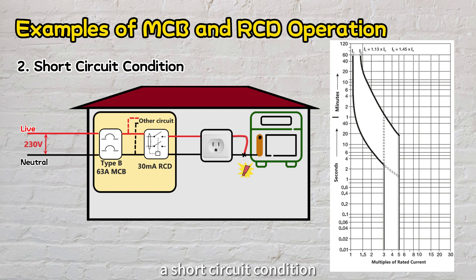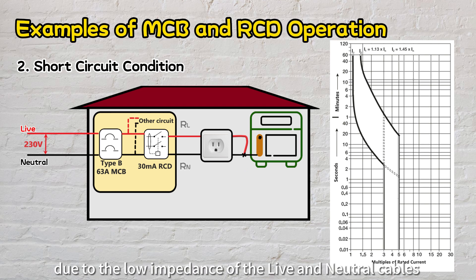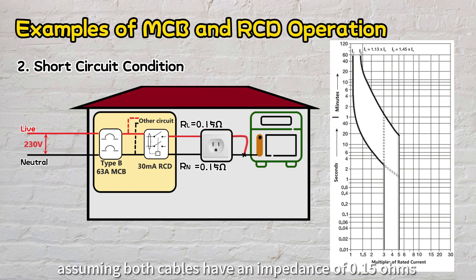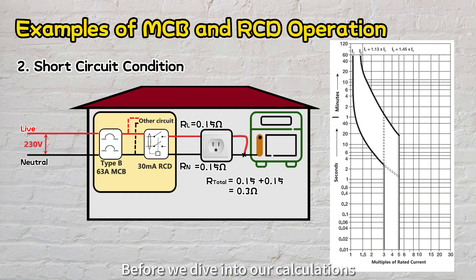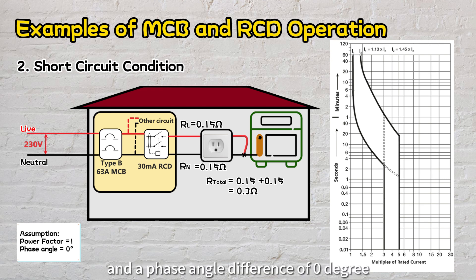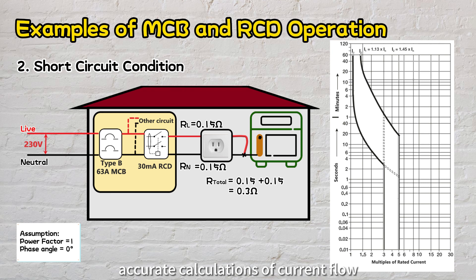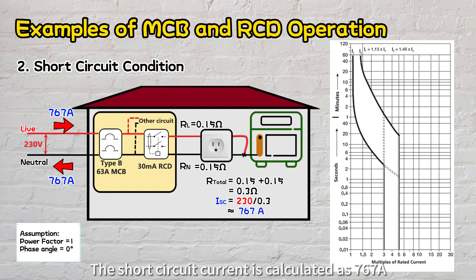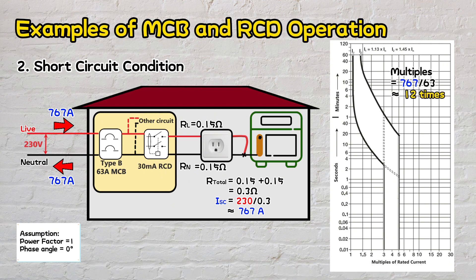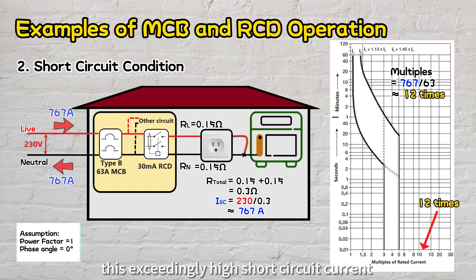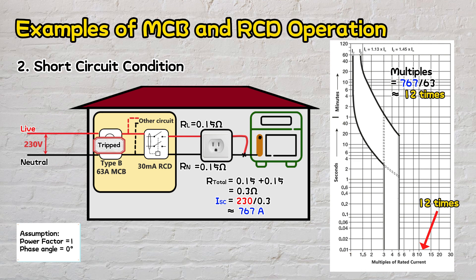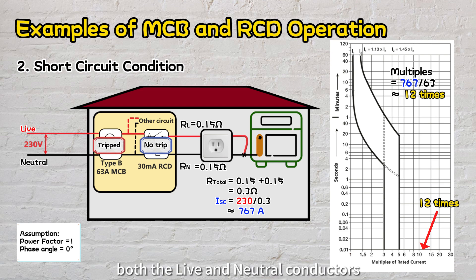Let's proceed to the second scenario: a short-circuit condition where the live cable accidentally makes contact with the neutral cable. The overall impedance is very low due to the low impedance of the cables — assuming both cables have an impedance of 0.15 ohms, totaling 0.3 ohms. Assuming a power factor of 1, the short-circuit current is calculated as 767 amps, approximately 12 times the 63 amps rated current. Referring to the tripping curve, this exceedingly high current will trigger the magnetic tripping mechanism and cut off the fault in less than 10 milliseconds, preventing a fire. Similar to the first scenario, the RCD will not trip because an equal current is flowing in both the live and neutral conductors.